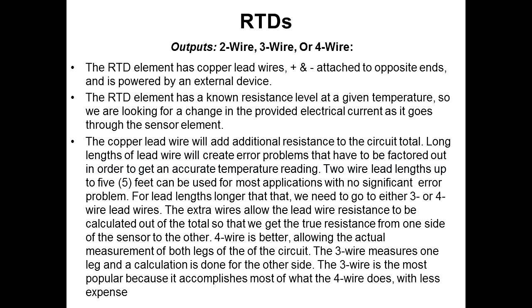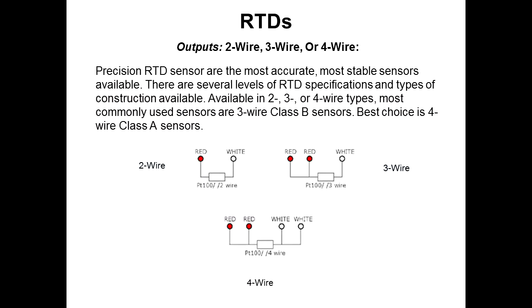The extra wires allow the lead wire resistance to be calculated out of the total so that we get the true resistance from one side of the sensor to the other. 4 wire is better, allowing the actual measurement of both legs of the circuit. The 3-wire measures one leg and calculates the other, assuming it's the same. It's not always true, but it's the most commonly used in industry because it accomplishes most of what a 4-wire does with less expense. So here we have the sensors, 2, 3, and 4 wire.